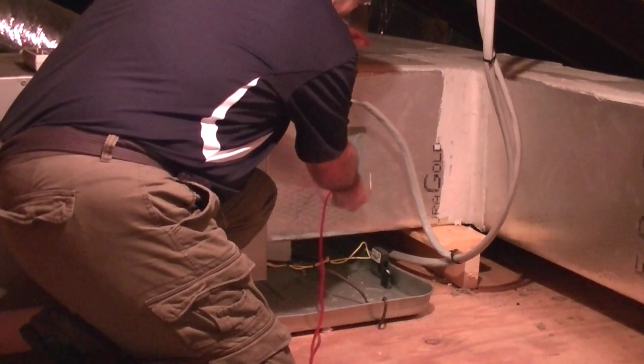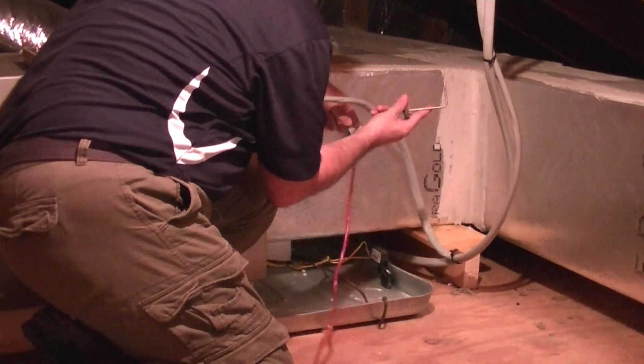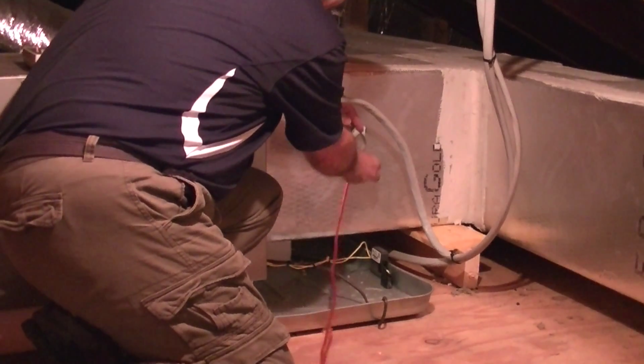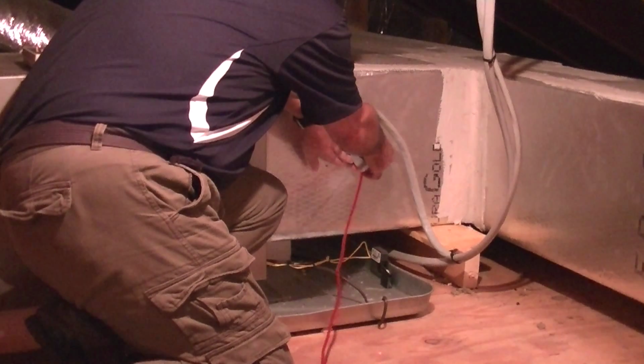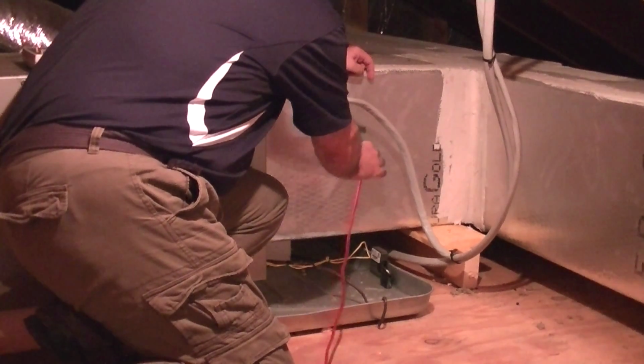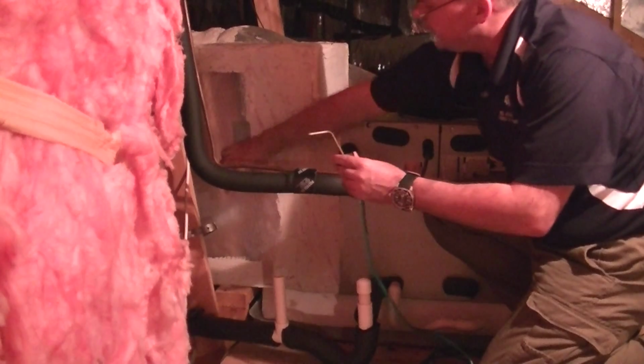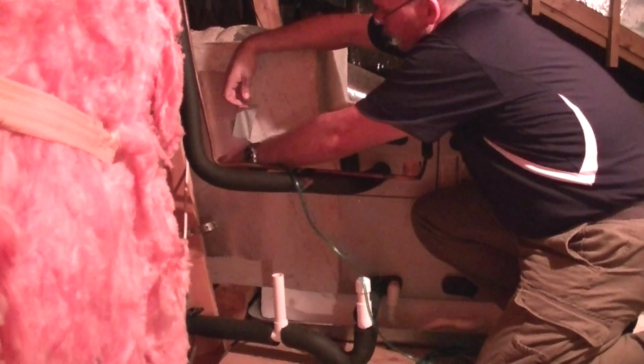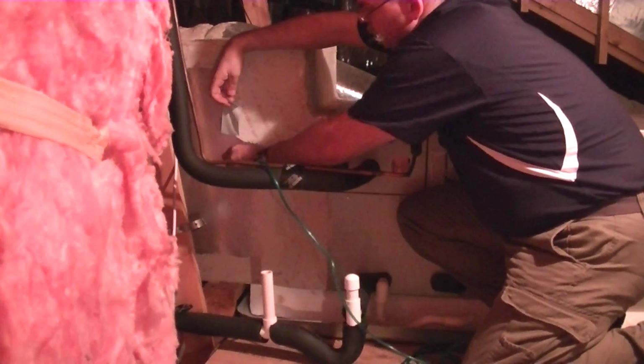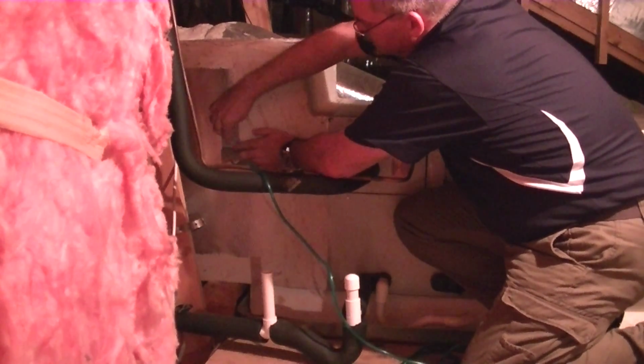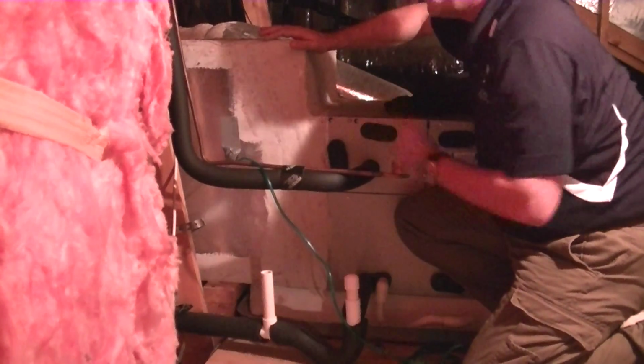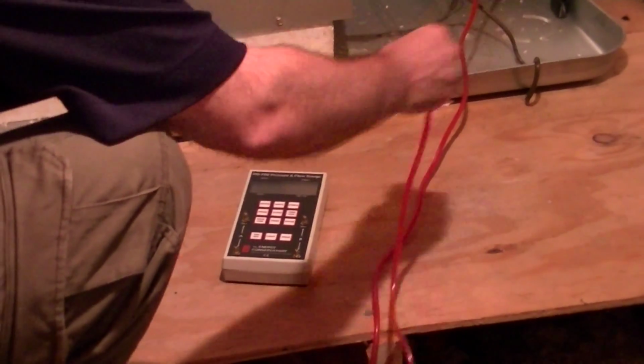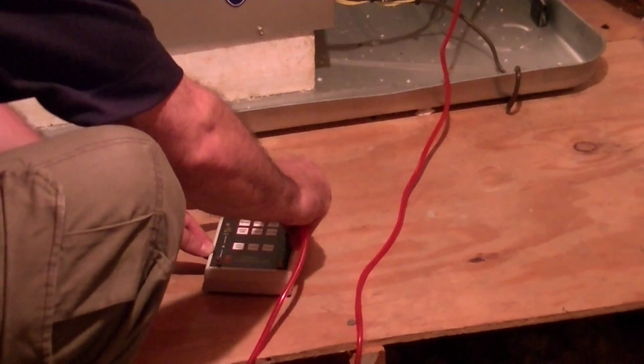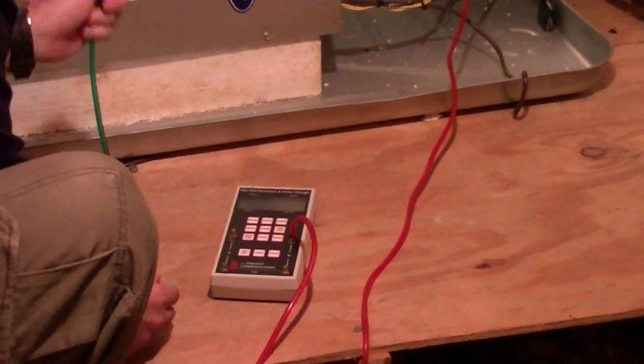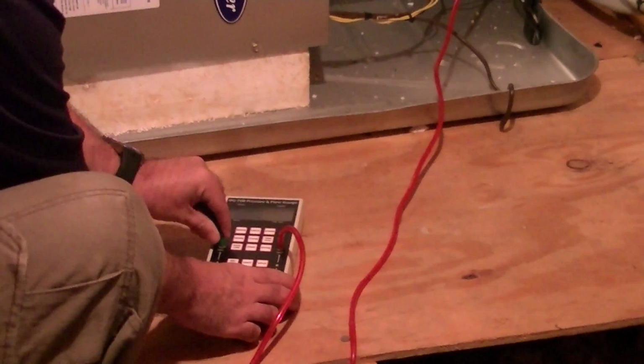So we're going to come over here, peel this tape back, and take this static pressure probe and insert it in the direction of the airstream, and use the tape to help secure that probe in that position. Now we're going to take this static pressure probe and insert it into the return plenum, again in the direction of the return airflow, securing it with the tape to hold it in that position. Now we're going to connect the supply side onto the top tap of the DG700 labeled input, and then connect the return side to the top tap on the other side labeled input.